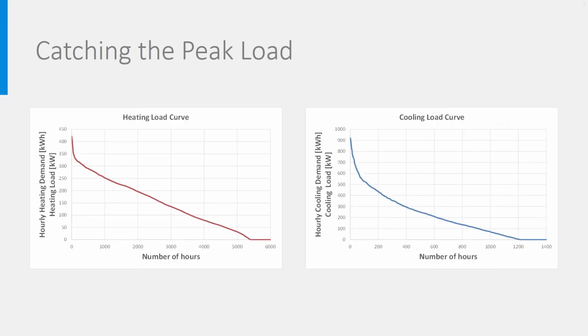Next to avoiding short cycles, a main advantage of a buffer is to provide peak load capacity in such a way that the generators can be sized smaller. A tank is much cheaper than a heat or cold generator, so that is financially advantageous. Let's use the load duration curves to look at how it works.